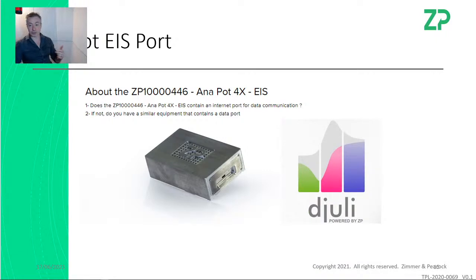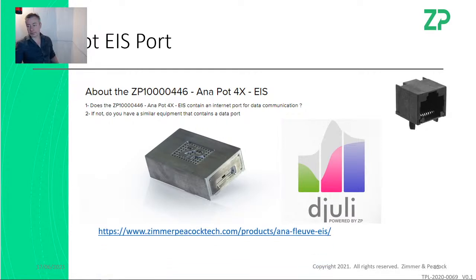It works now with djuli as well, in terms of we're now able to take EIS data and put it up into djuli. The question is, does it have an Ethernet port? And the sad answer is, unfortunately, it doesn't have an Ethernet port. And we don't have any models with Ethernet ports. I know this was a big thing. I have owned these potentiostats as well with these Ethernet ports, but we don't have an instrument with an Ethernet port. We have Bluetooth connectivity, but we don't have Ethernet ports. So short answer, but I do appreciate it.